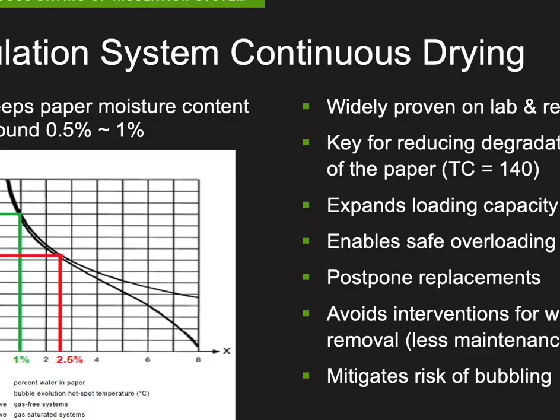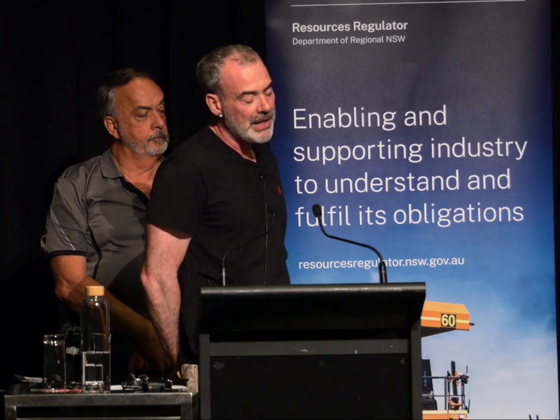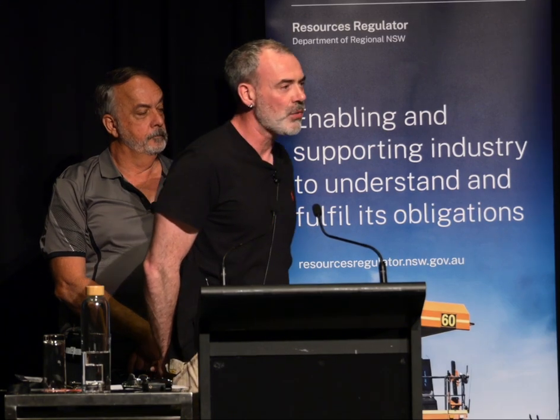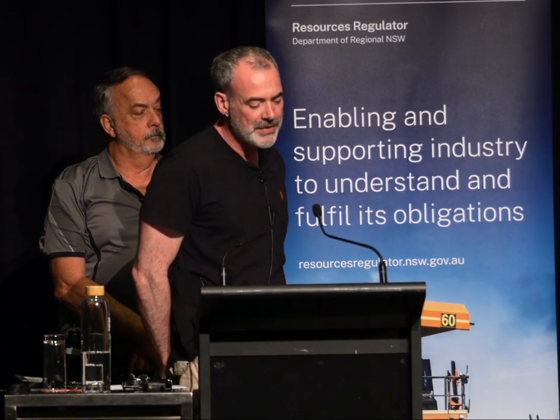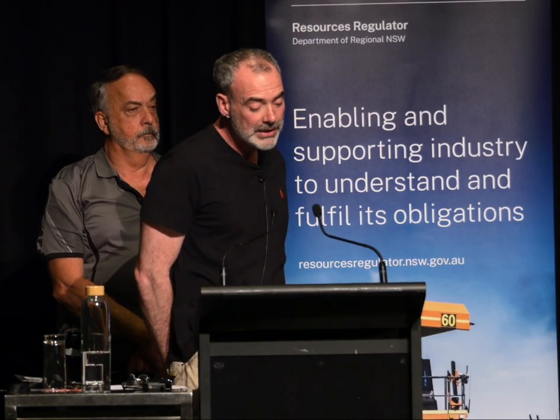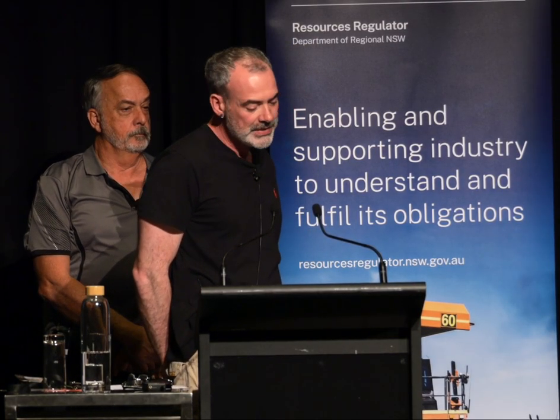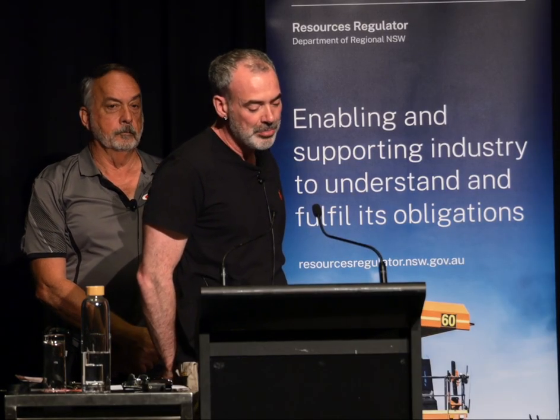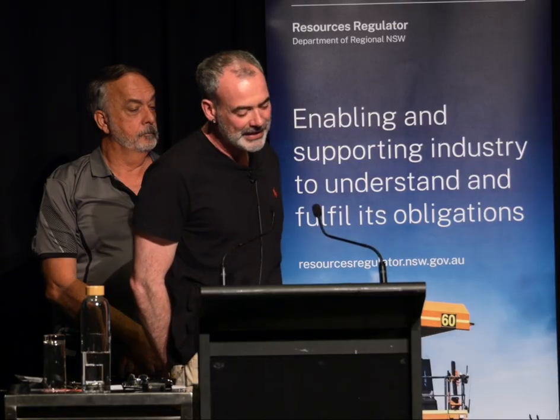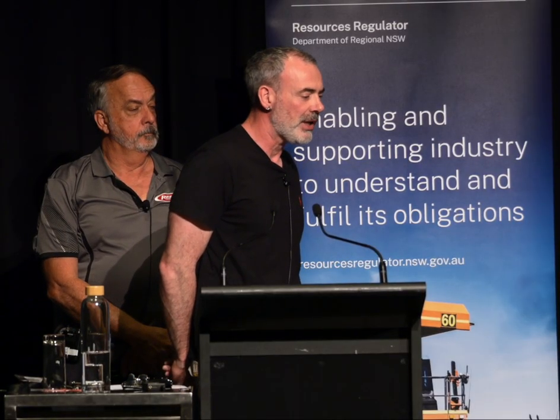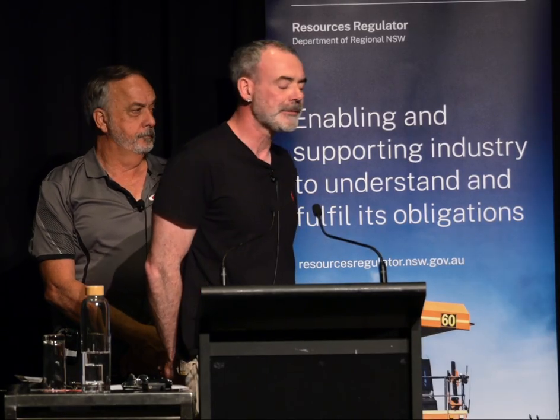So during operation, you may need to apply filtration to mineral oil-filled transformers to reduce water and acid levels. Drier solid insulation is a consequence of using natural ester and also synthetic ester. The solid insulation in the transformer should last longer. Slower degradation means postponing replacements of transformers, that's potentially a cost saving, which balances out the increased cost of the ester fluid.